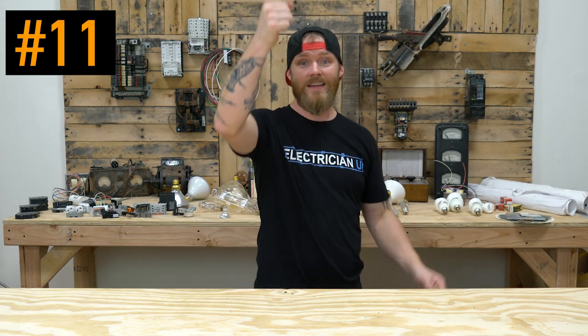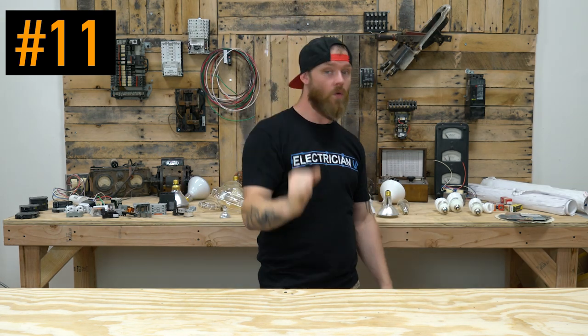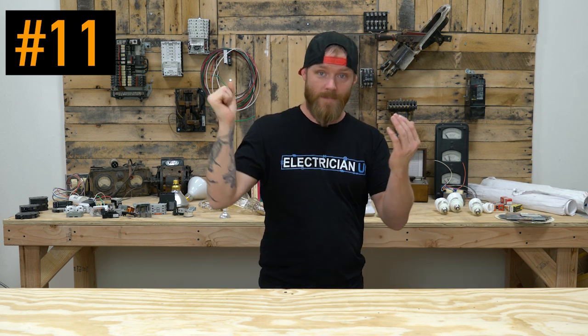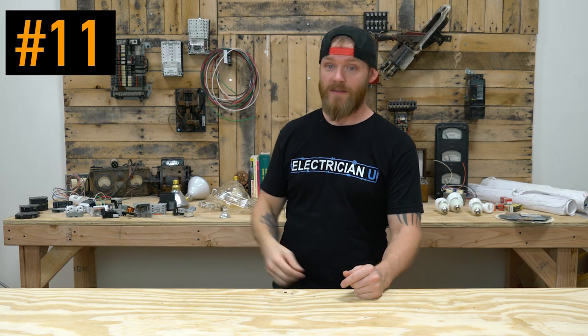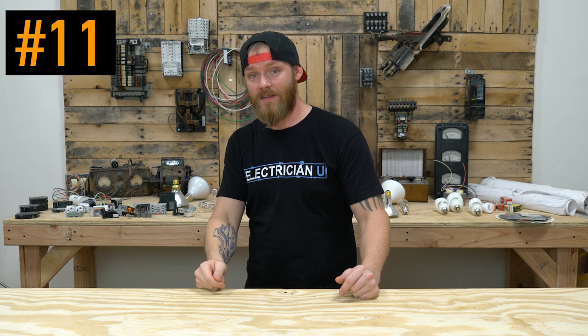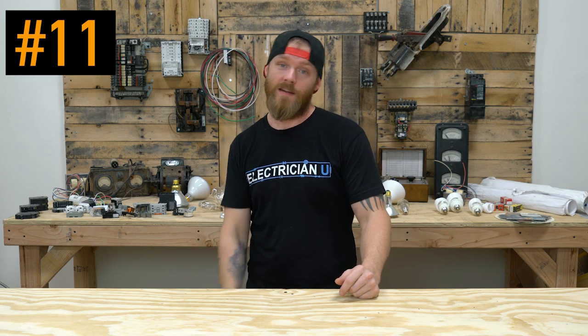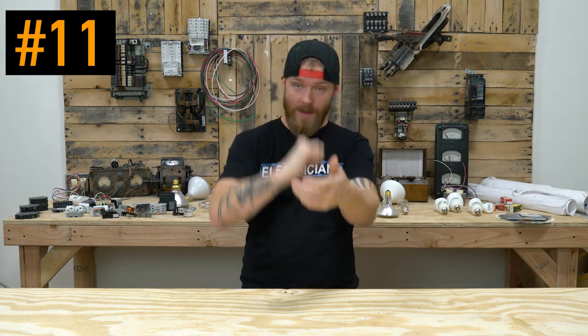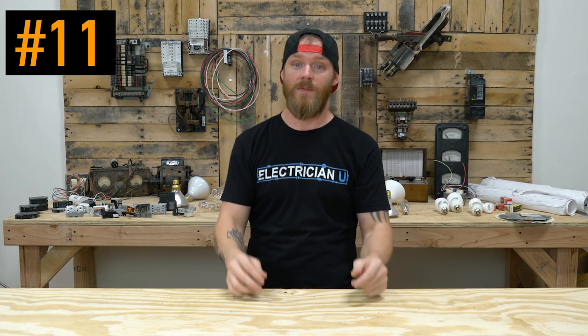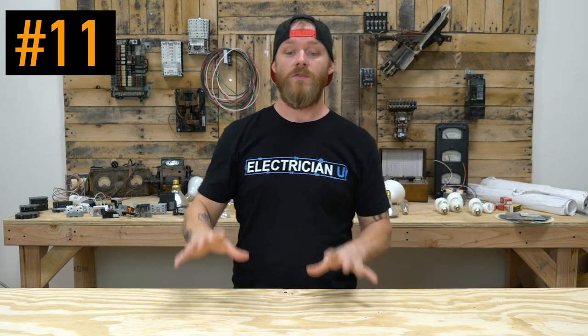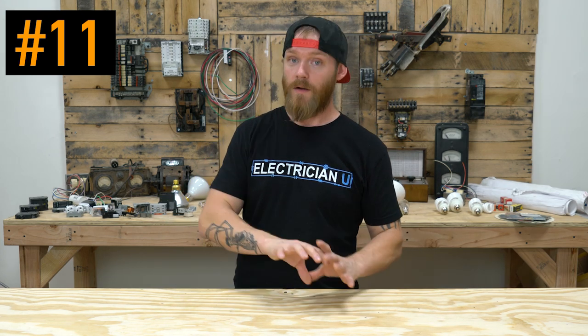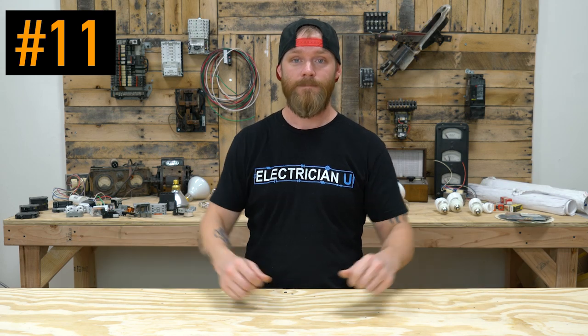But the main disconnect out at your service that shuts your whole entire building off, that is a disconnecting means. The furnace, the little switch that you have, if you have a gas furnace, that 110 switch, that's a disconnecting means. If you have an electric furnace and you have huge wires going to it and you've got that big, huge disconnect, that's a disconnecting means. So anything that is going to disconnect the conductors that are feeding the load so that they don't have power on them anymore, that is a disconnecting means.